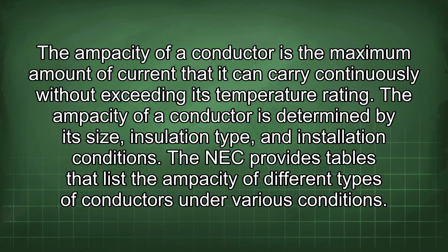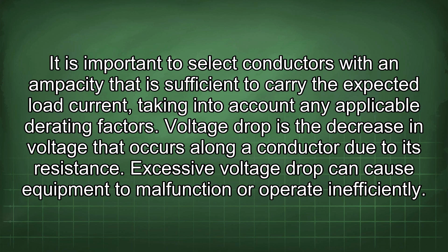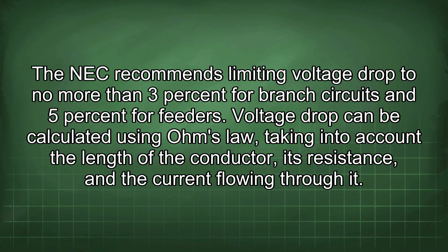Voltage drop is the decrease in voltage that occurs along a conductor due to its resistance. Excessive voltage drop can cause equipment to malfunction or operate inefficiently. The NEC recommends limiting voltage drop to no more than 3% for branch circuits and 5% for feeders. Voltage drop can be calculated using Ohm's law, taking into account the length of the conductor, its resistance, and the current flowing through it. Wiring methods refer to the various ways in which electrical conductors can be installed.